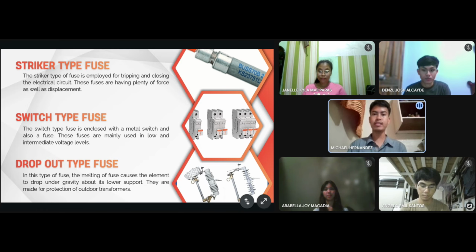So the next one is the striker type fuse. It's a special kind of fuse designed not only to protect electrical circuits from overcurrent, but also to provide a quick and visible mechanical action when it blows. What makes it unique is the striker pin, a small spring-loaded part built into the fuse that pops out when the fuse operates. This popping action can be used to trigger a switch, indicator, or mechanical interlock, helping operators instantly know which fuse has blown and even disconnecting power automatically for extra safety.